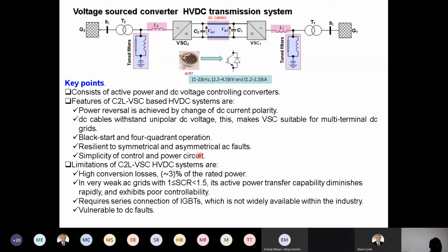And also it's resilient to symmetrical and asymmetrical AC faults, as we will see later. And also it has simplicity of the control and the power circuits compared to the latest topologies. But its limitation, it has high losses, around 3%. Yes, 3% in low voltage is not a big issue, but 3% in 1,000 megawatts is 30 megawatts. So it's significant in high power applications.